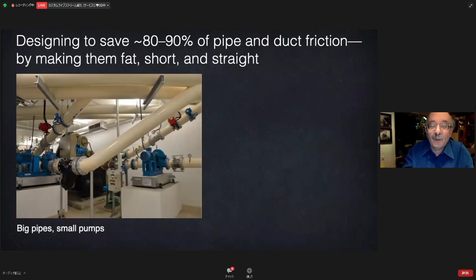So in this example, on the left, the low friction pipes make the blue pump so tiny that it looks like a decimal point error, and it's raised up to meet the pipe rather than conventionally dipping the pipe down to meet a pump on the floor. On the right, these 10 chillers, normally in a neat row, are staggered to eliminate the pipe elbows and their friction.